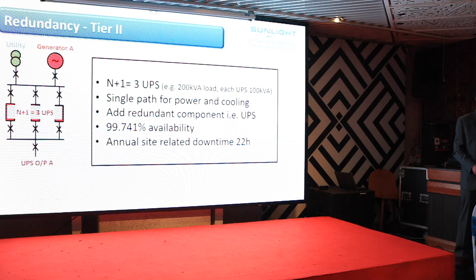If you have an N plus 1, then I use the same load that is required. You actually add a second critical distribution path. In this case, you add a second one, but you keep one as active. Every time you use one. If anything happens, you change over.